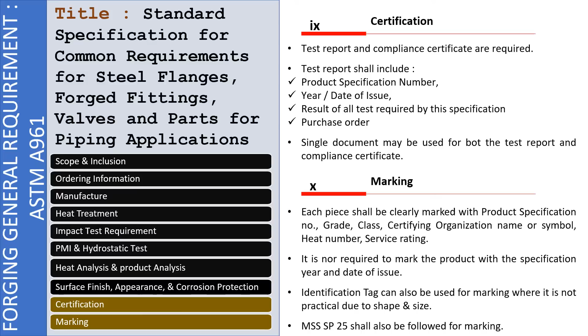Also, MSS SP-25 is always there, where all these marking requirements, what has to be marked and how it has to be marked, are detailed very nicely. So we have to refer to this standard when we are talking about marking for any fitting, flange or valve. An identification tag can also be used for marking where it is not practical due to shape and size. If the shape is complicated or small, then an identification tag can be associated with that particular item so that we can identify it at site. So these are a few of the general requirements with respect to marking and certification.